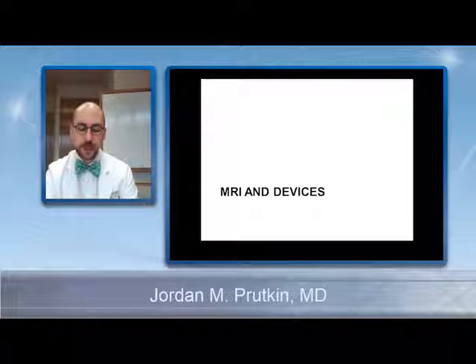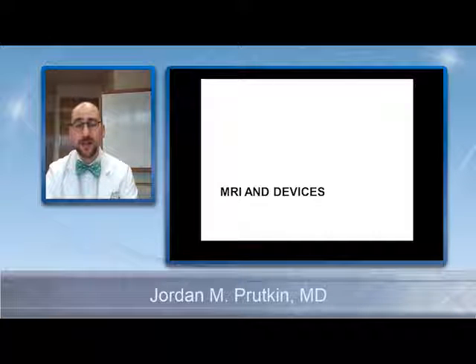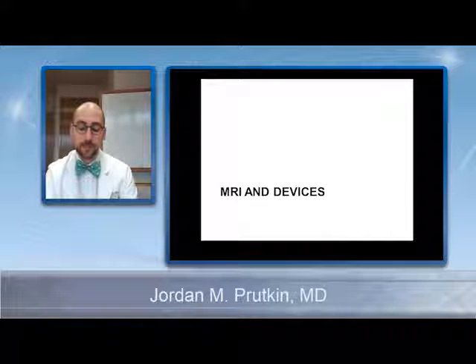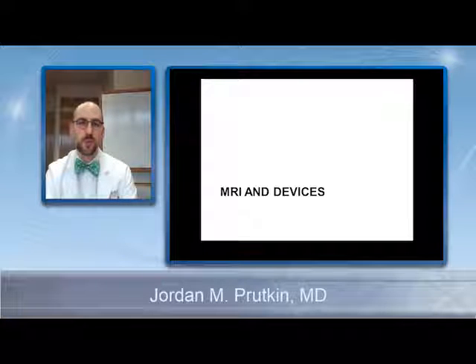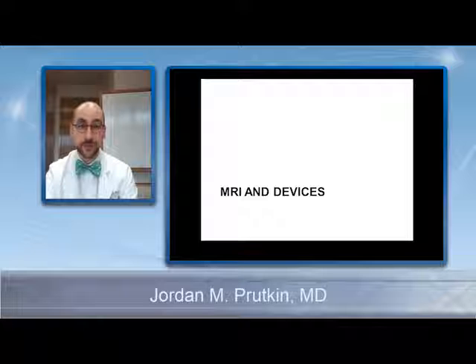There's actually even now devices where you can pre-program an MRI setting, and the device is able to tell that the patient has gone into an MRI scanner and can automatically change its settings, so that you don't even need to have someone program it ahead of time, or at least not immediately ahead of time, as long as those settings have been programmed either at the time of implant or at a clinic visit, so that the device knows what to do once it enters the MRI environment. There are a couple ICDs that are FDA approved to be MRI conditional that can go in the MRI environment also. Not every manufacturer makes those yet, though.